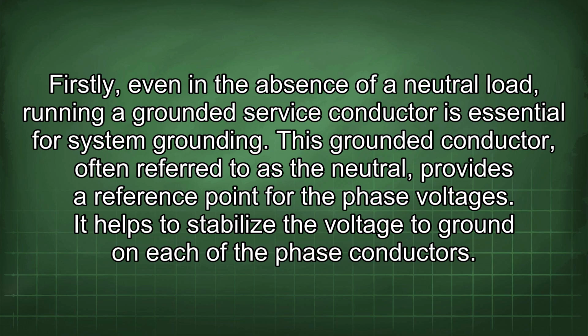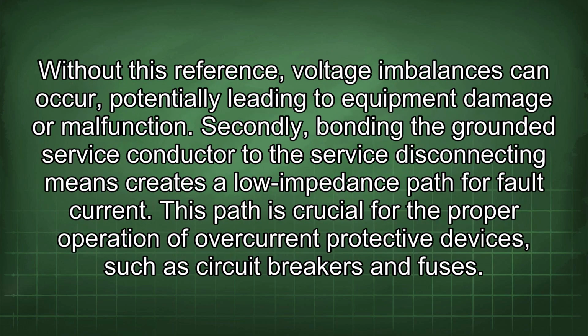This grounded conductor, often referred to as the neutral, provides a reference point for the phase voltages. It helps to stabilize the voltage to ground on each of the phase conductors. Without this reference, voltage imbalances can occur, potentially leading to equipment damage or malfunction.